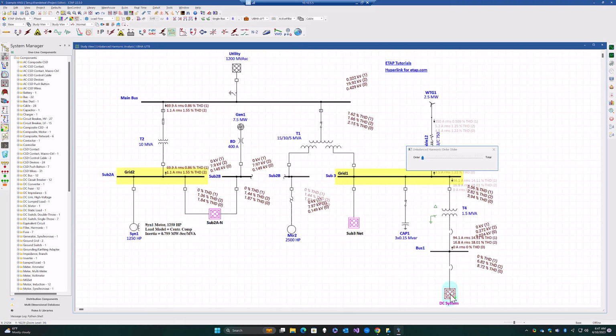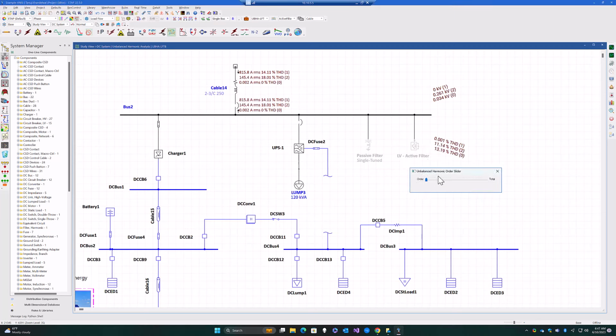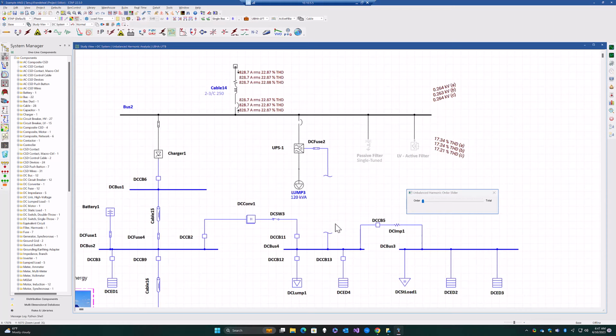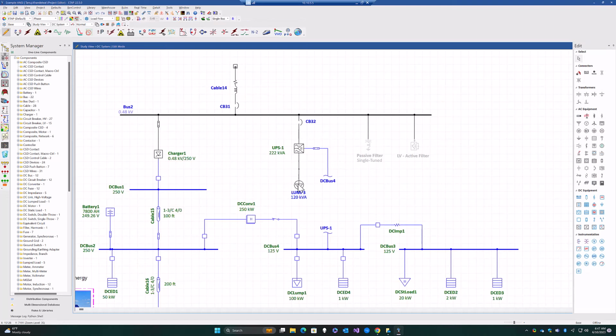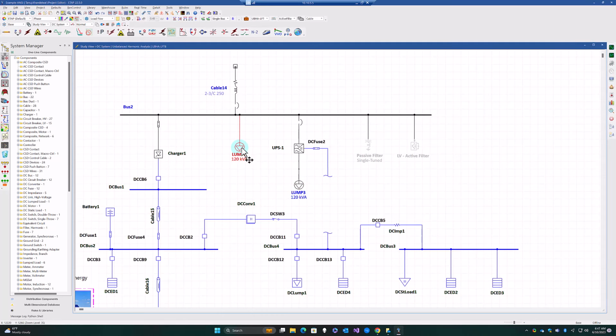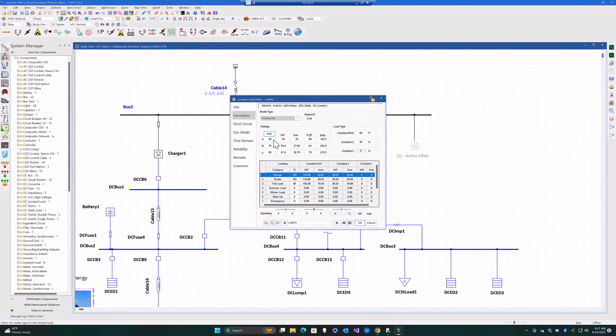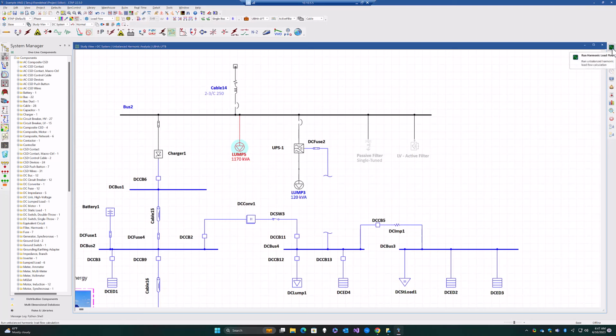Now let's take a look at the DC system that we have very quickly, and I'll switch back into our all phases view just to make it a bit easier to understand what's going on. Let's copy and paste this load here, and we'll connect this load to our bus 2 and make sure that when we are utilizing this load, we create an unbalanced condition in our system. This unbalanced condition will be substantially unbalanced on phase B. Let's run our simulation again.